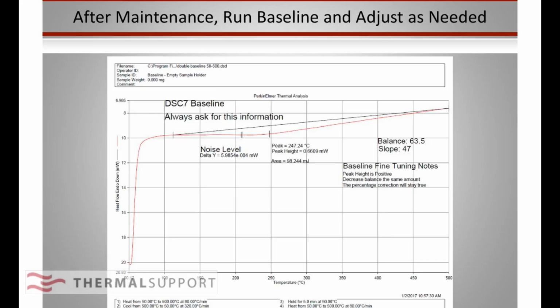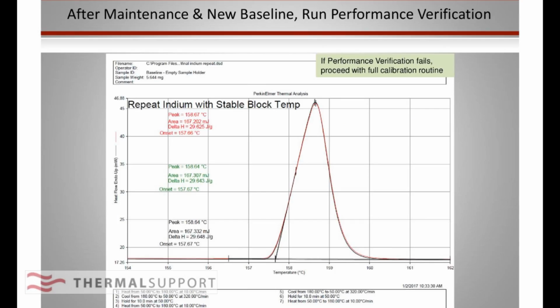Then, and a lot of y'all are going to be different. If you're running from -50 to 150, you want a baseline over that range. If you're going to run from 50 to 250, you run a baseline over that range. Full range may work perfect for you, but it may not. You may need a smaller range baseline. And then you want to go ahead and do a quick performance verification, make sure you're working right.